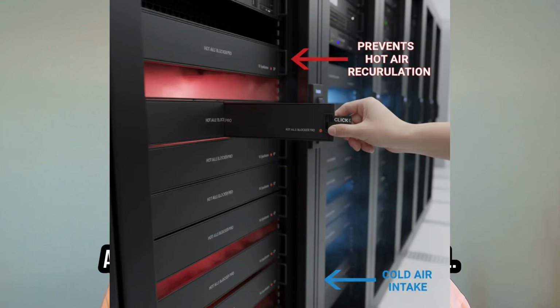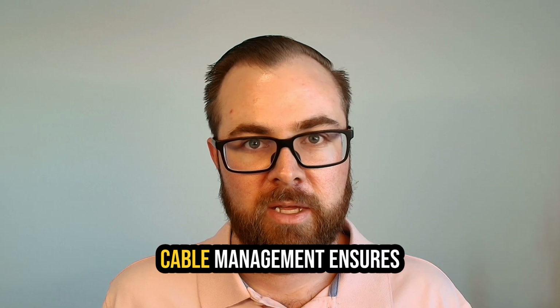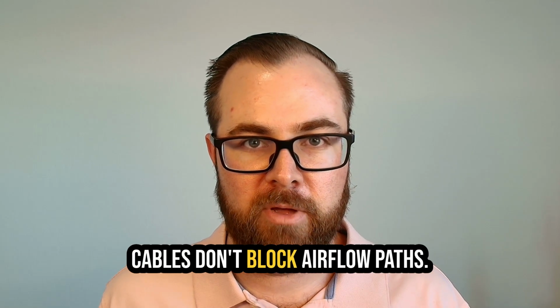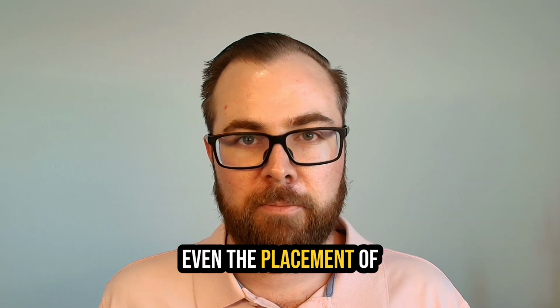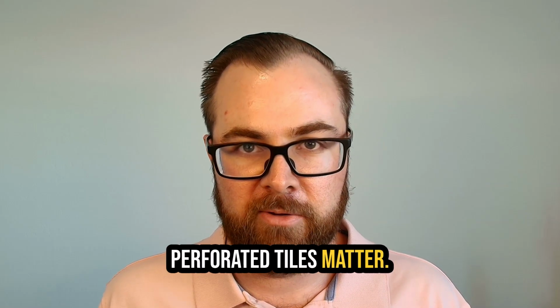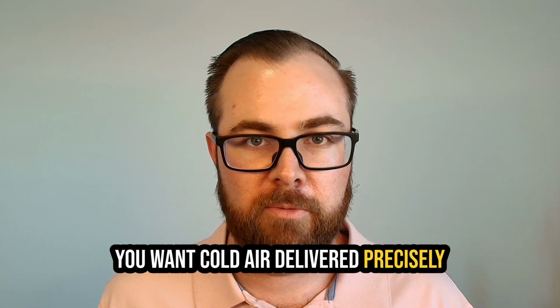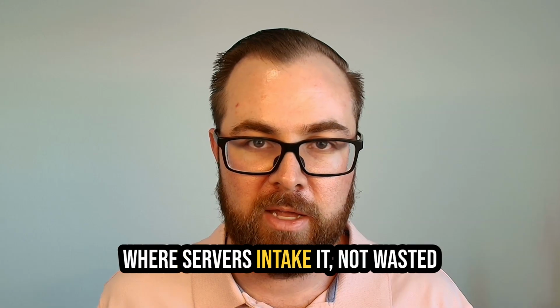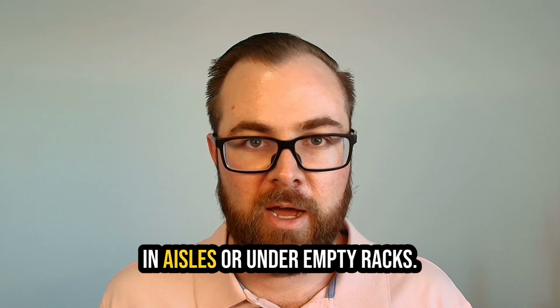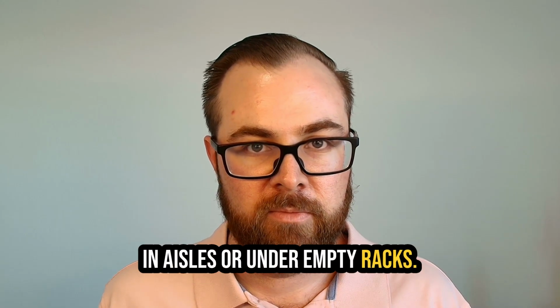Airflow management is equally critical. Blanking panels fill unused rack spaces to prevent air recirculation. Cable management ensures cables don't block airflow paths. Even the placement of perforated tiles matters. You want cold air delivered precisely where servers intake it, not wasted in aisles or under empty racks.